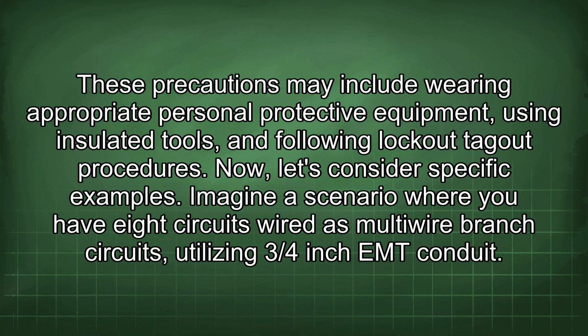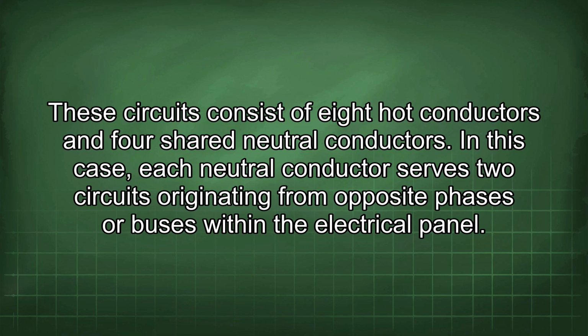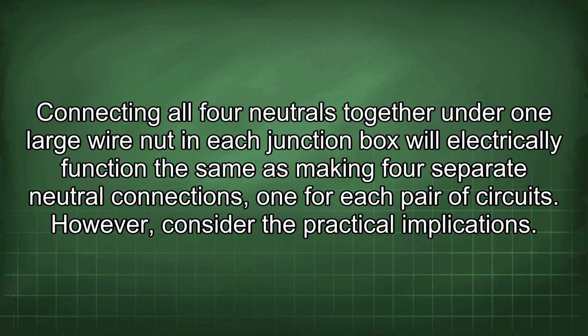Imagine a scenario where you have 8 circuits wired as multi-wire branch circuits, utilizing 3/4-inch EMT conduit. These circuits consist of 8 hot conductors and 4 shared neutral conductors. In this case, each neutral conductor serves 2 circuits originating from opposite phases or buses within the electrical panel. Connecting all 4 neutrals together under one large wire nut in each junction box will electrically function the same as making 4 separate neutral connections, one for each pair of circuits.